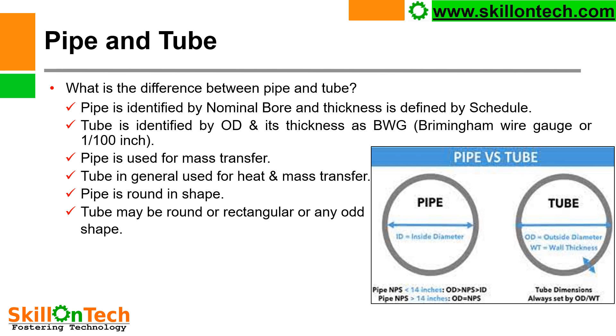What is the difference between pipe and tube? In a pipe, the ID (inside diameter) is measured, while in a tube, the OD (outside diameter) is measured. Pipe is identified by nominal bore and thickness as defined by the schedule, which provides the thickness of the pipe. Tube is identified by OD and its thickness in Birmingham Wire Gauge (BWG) or 1/100 inch. Pipe is used for mass transfer, while tube is generally used for heat and mass transfer. Pipe is round in shape; tube may be round, rectangular, or any other shape.